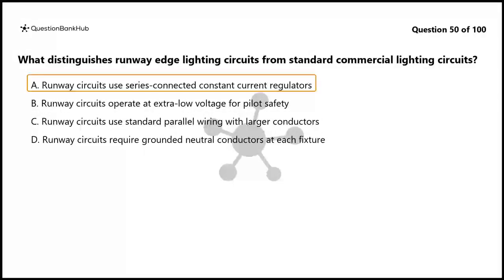The correct answer is A. Runway circuits use series-connected constant current regulators. Airfield lighting uses series-connected circuits with constant current regulators. Unlike parallel circuits, series circuits maintain consistent brightness across all fixtures regardless of cable length. Current regulators adjust voltage to maintain specified current levels.